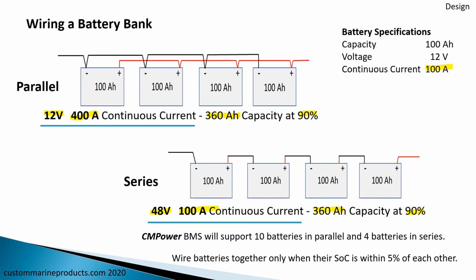For the CMPower batteries, we put in a BMS that will allow up to 10 batteries in parallel and up to 4 batteries in series. We also recommend, and this is very important, we're going to talk about this more later, that batteries should be about the same state of charge when we wire them together, within 3 to 5% state of charge.